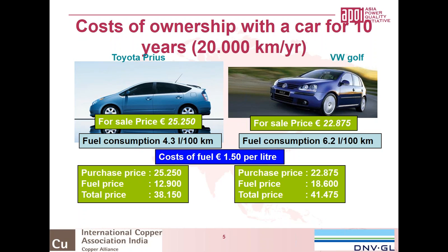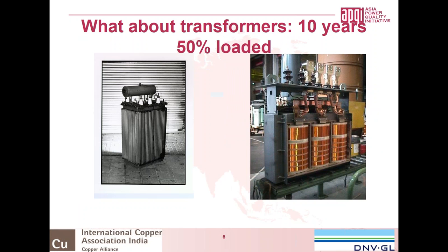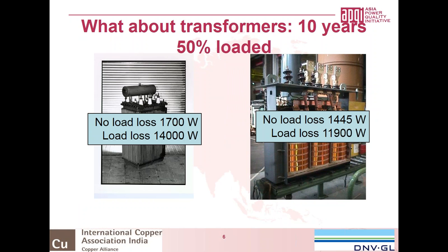1,000 euros. That could be the same for transformers. If you have two transformers, and on the left side you see a very old one and on the right side you see a very new one. If you look at both transformers, of course, both transformers do have a kind of price and also some losses which they have. And in transformers we have two kinds of losses. We have the no load losses and we have the load losses. Later on we will discuss them in more detail.